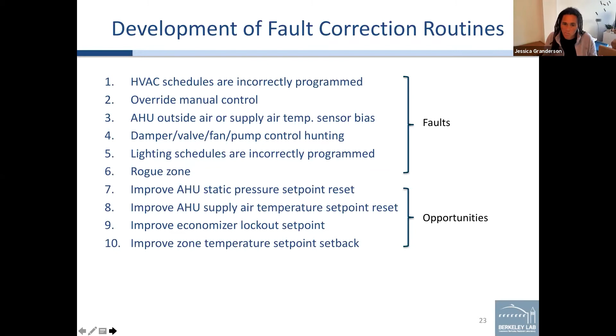Here are some of the correction routines we're working with across that set of partners. They're categorized into things like hard faults versus those that represent more opportunities to improve further. You'll see problems with biased sensors, incorrectly programmed schedules, rogue zones driving system operation to the extreme. Opportunities are all around reset strategies, lockout set points on economizers, and zone temperature set points, ensuring those are appropriately set and set back.